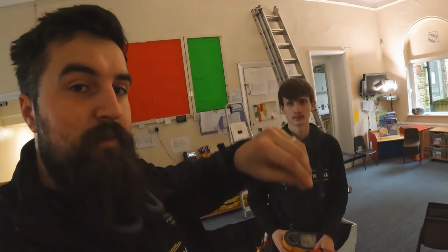Right then, with testing, what's the best bet when we look into these circuits? Normally if it was one circuit, you've got to think how it's wired. It could be from your fuse board, feeds to switches in and out, and then a cable up to your light to make it work. You could go into that switch and disconnect the feeds coming in, and then you'd have a cable going back to the fuse board and a cable going out into the circuit, off to the next switch. That way you'd have a good side and a bad side.